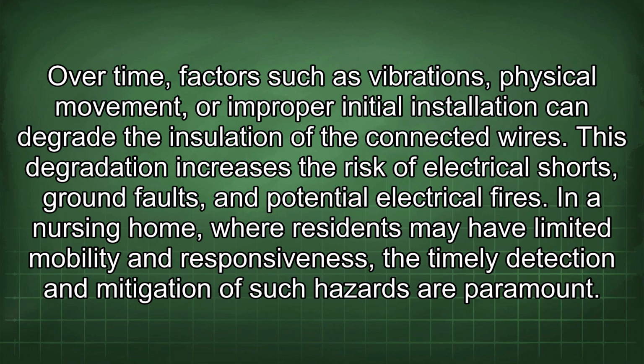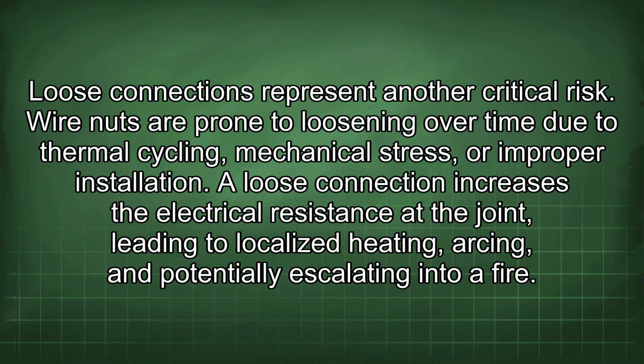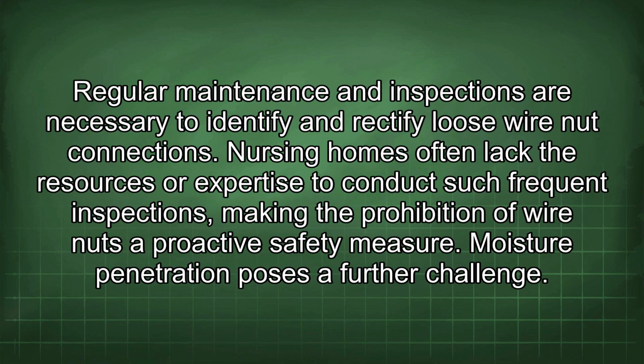Loose connections represent another critical risk. Wire nuts are prone to loosening over time due to thermal cycling, mechanical stress, or improper installation. A loose connection increases the electrical resistance at the joint, leading to localized heating, arcing, and potentially escalating into a fire. Regular maintenance and inspections are necessary to identify and rectify loose wire nut connections. Nursing homes often lack the resources or expertise to conduct such frequent inspections, making the prohibition of wire nuts a proactive safety measure.